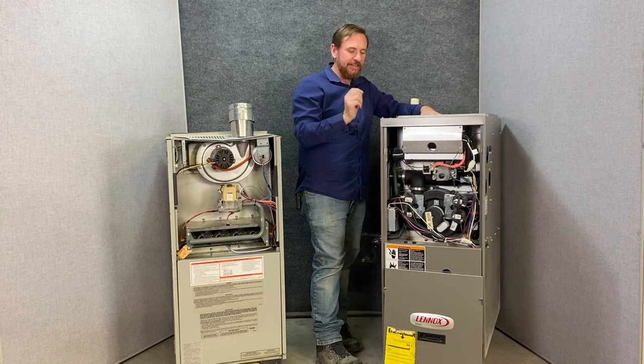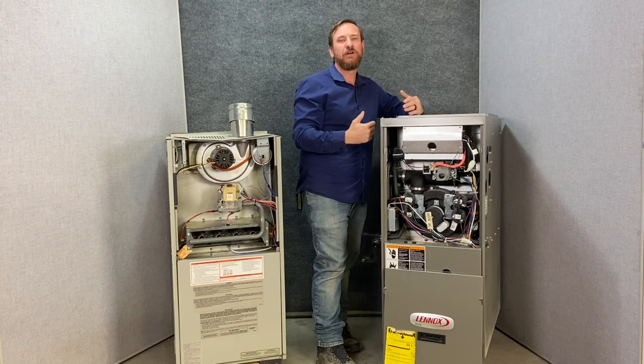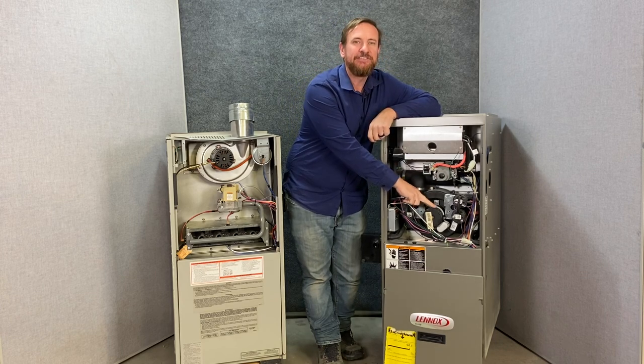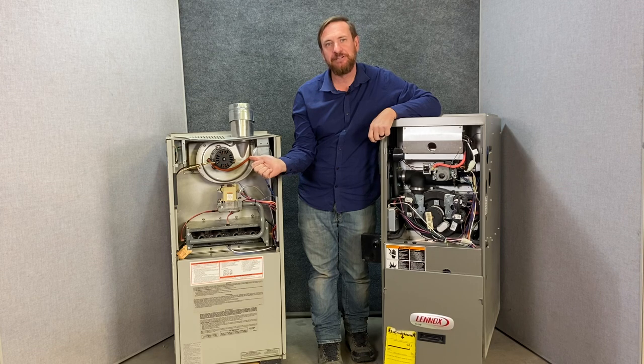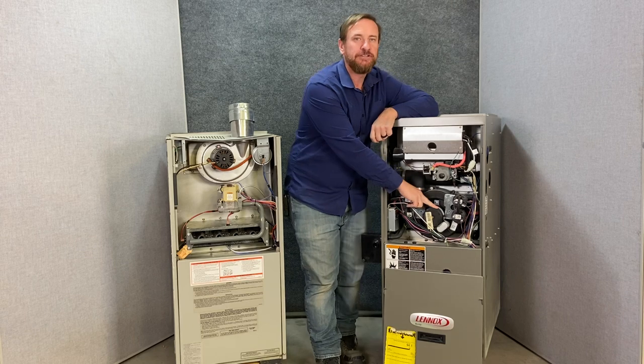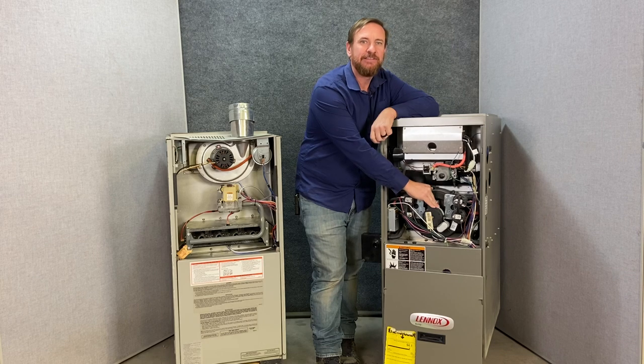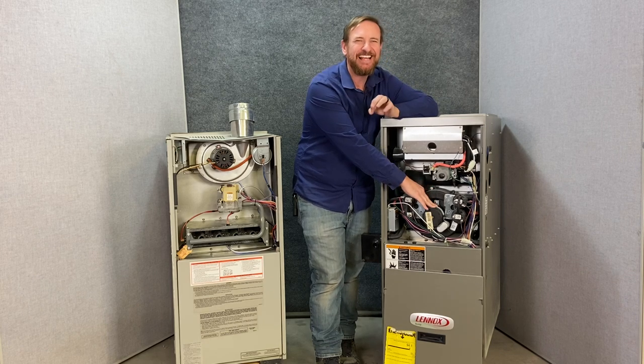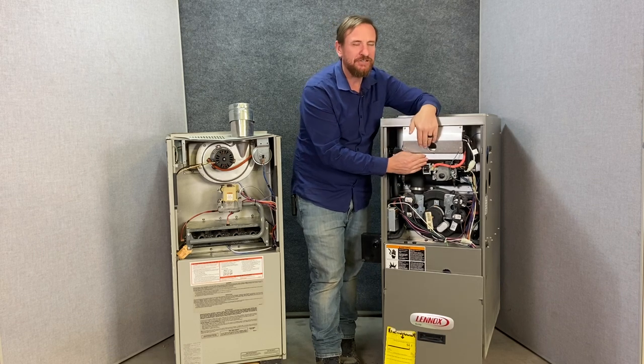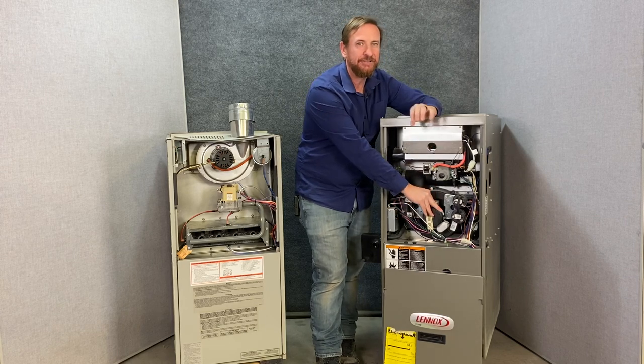When those really cold days hit, the furnace goes into high fire and uses full capacity. To make that work, the inducer fan motor is now a two-speed motor. The IFC needs to know this motor is on low speed when we have low fire — the engineers have designed the motor speed and hole sizes to pull a precise amount of air, so the combination gas valve opens a precise amount. We have low pressure switches to confirm this: when on low fire, only the low pressure switch closes and only the low side of the solenoid valve opens for gas flow.